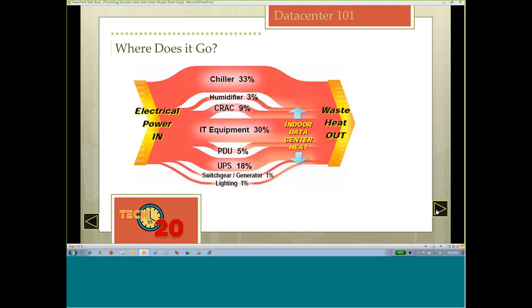We had a customer where they were actually running somewhere in the neighborhood of almost 50% loss in their transfer, then realized they had a bad transformer. What it came down to is, I think we figured it was $390 a day that they were losing just in power loss alone. So it all adds up, no matter what you're doing.